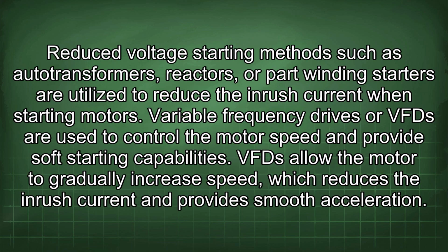Reduced voltage starting methods such as auto transformers, reactors, or part winding starters are utilized to reduce the inrush current when starting motors. Variable frequency drives, or VFD, are used to control the motor speed and provide soft starting capabilities. VFD allow the motor to gradually increase speed, which reduces the inrush current and provides smooth acceleration.